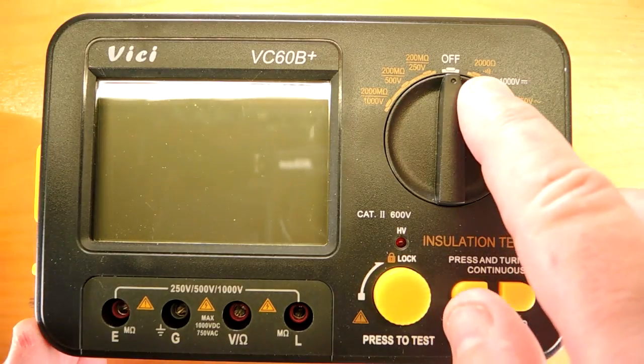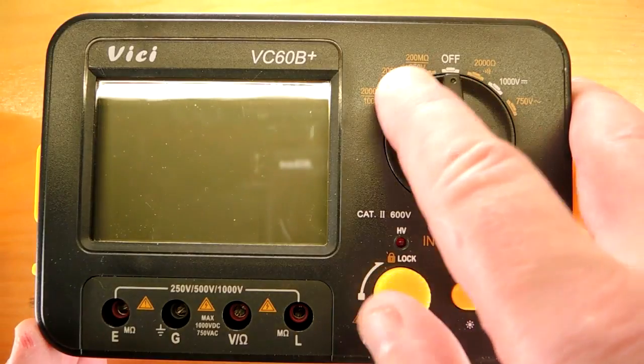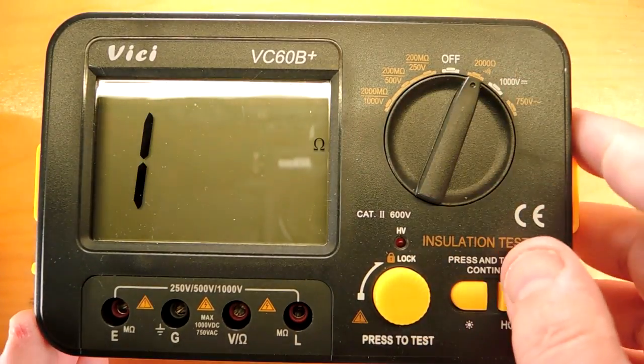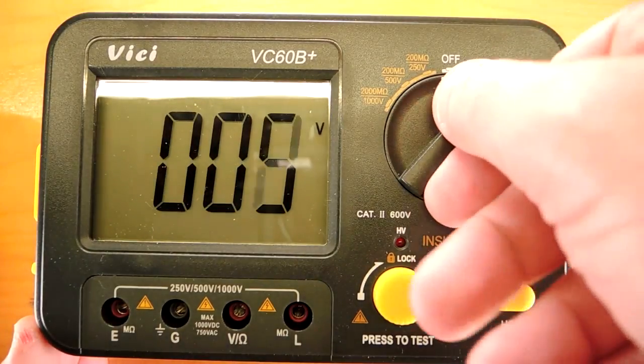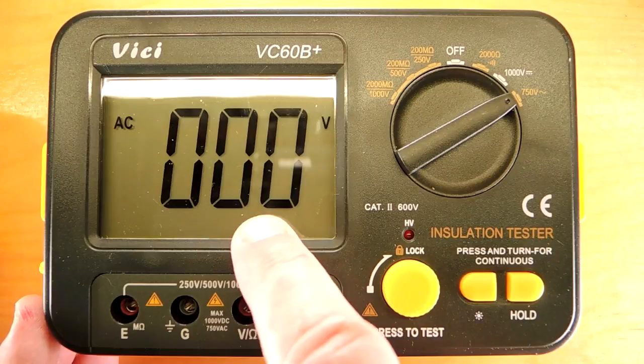So just to review the operation, there's a normal multimeter function on this side, and then the insulation testing or mega-ohm meter on this side. Over here we have an ohm meter, a DC meter, and an AC meter. There's no digits, so the resolution of this side isn't particularly great. But what's really special about this meter is on this side.